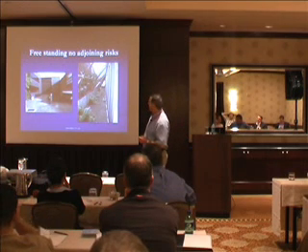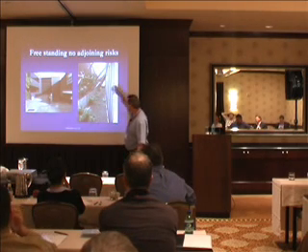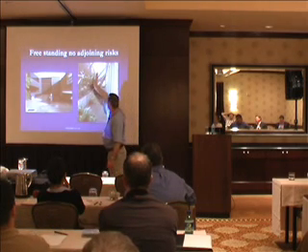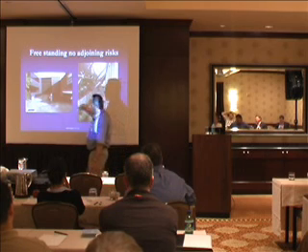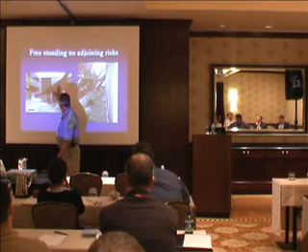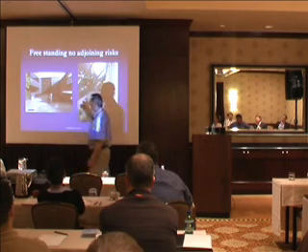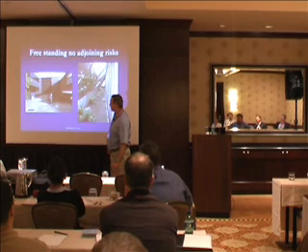So, freestanding and no adjoining risks. That's the airspace behind the building, and courtesy of the government, we have a very nice secured, screened-off security wall here. We have another caged area off here. We haven't cleaned it up, as you can see. It will improve. Down here, it's not ideal, but we have an air gap between these two buildings, and each has its own walls. Our vault actually runs down that wall, so we have this whole warehouse area from a risk assessment point of view. The rear of the building also has a sprinkler system running on the back, which is one thing that was nice to have.